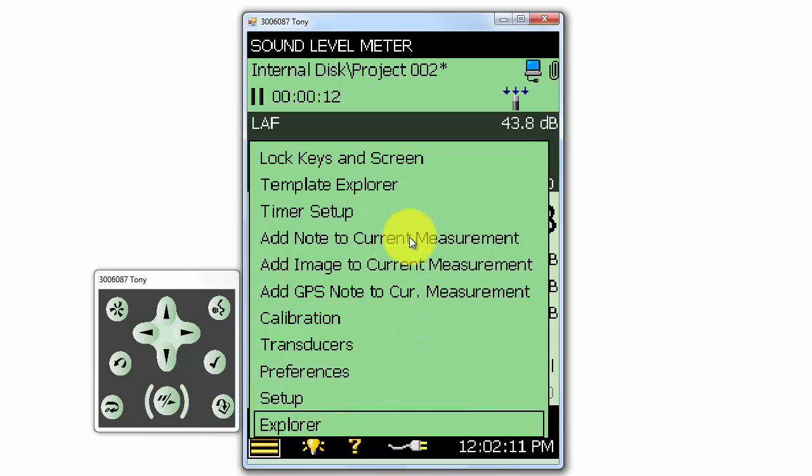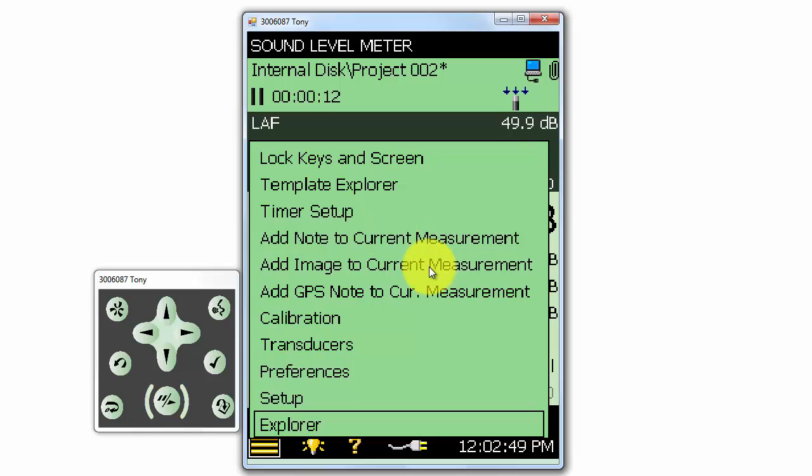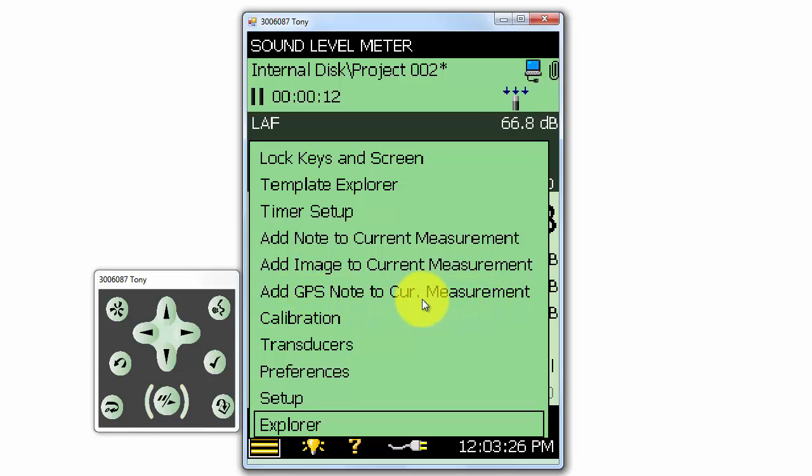For record keeping, we can add a note to our current measurement if we click on Add Note to Current Measurement. We can also add an image to the current measurement on the 2270, or we can make a record of the meter's GPS location if we have a GPS receiver plugged into the meter.